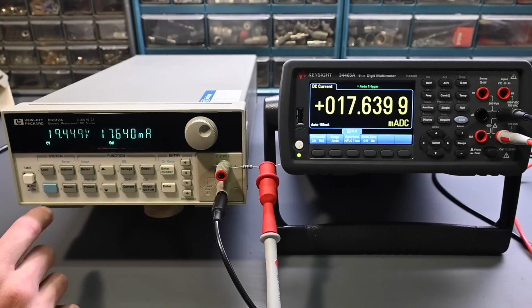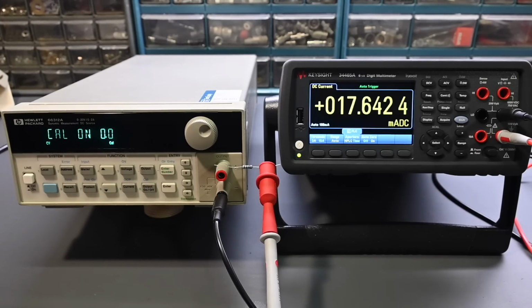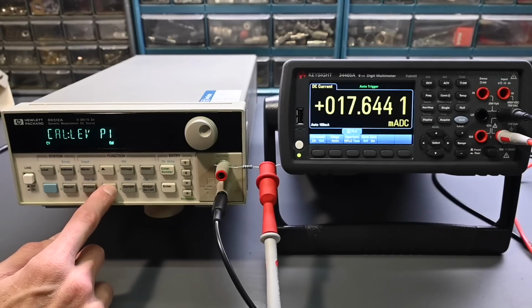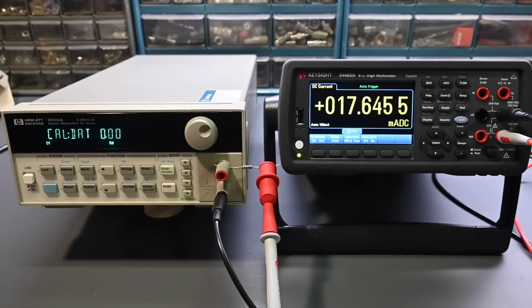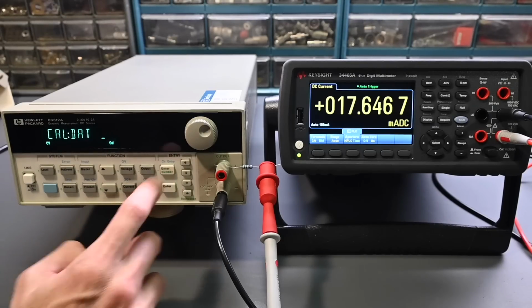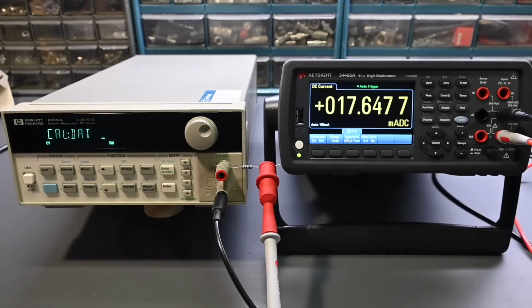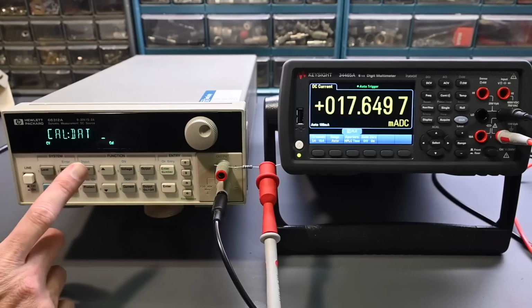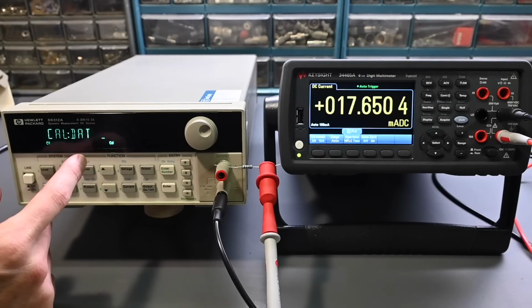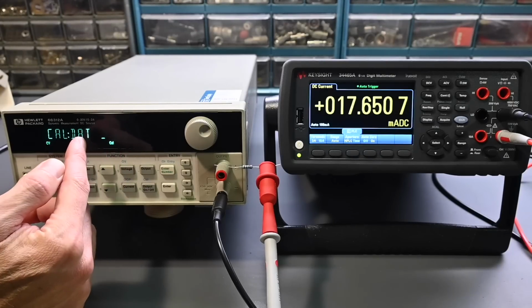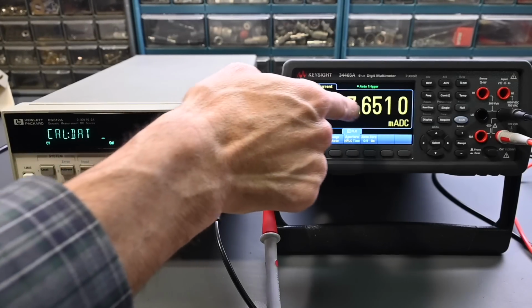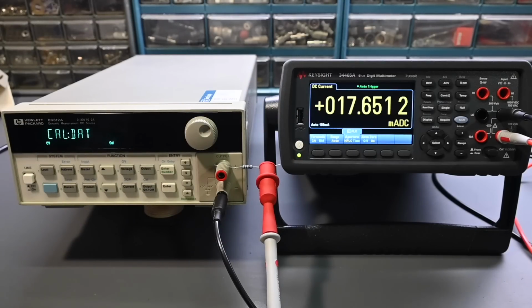It says press Shift Cal, and scroll to cal data, and then press enter number. And then it says to wait till it stabilizes and then enter the number on the display. Now, something I'm not sure of here, I think this should be entered as milliamps. Okay, this is displaying milliamps, but over here, I think this is in amps, so we need to put the decimal point and then over for the 17 milliamps that we're seeing there. I believe that's how this is supposed to be done. They're not clear on that, but let's try that here.